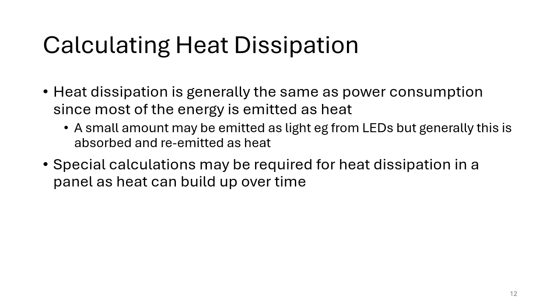Now there may be additional calculations you need to do. Heat can build up in a panel over time, and that might require more heat dissipation. And also you might need to consider what the external heat sources are. You assume that a panel is able to radiate heat outwards, but if it's in sunlight, it might even be absorbing heat, and that might also cause the panel to heat up. So there may be additional considerations. But generally, you calculate the power consumption, and that gives you your heat dissipation in watts as well.